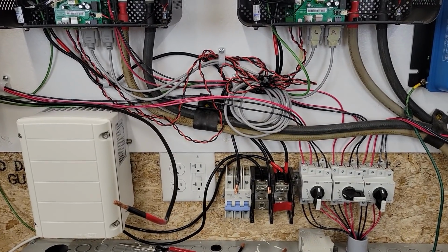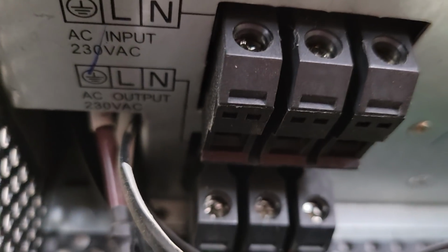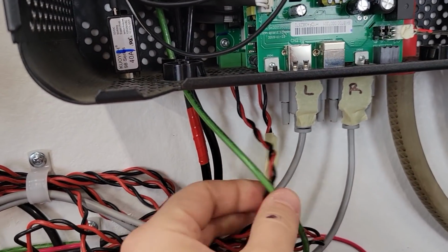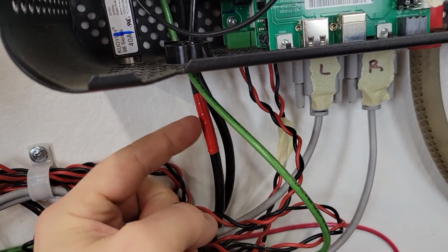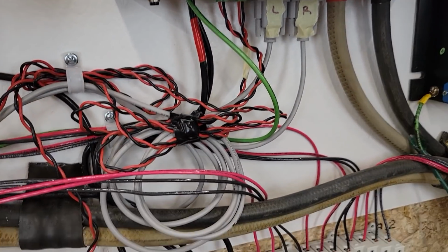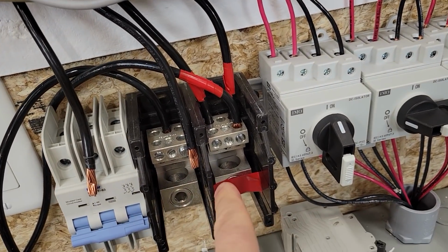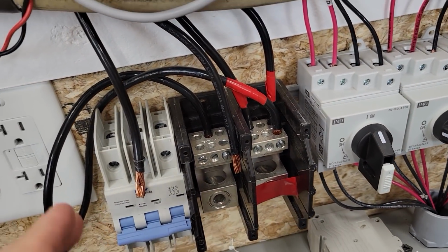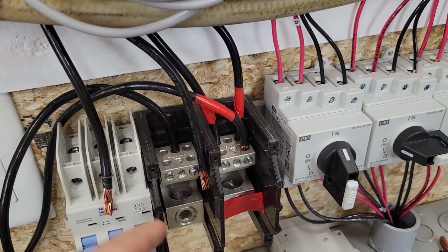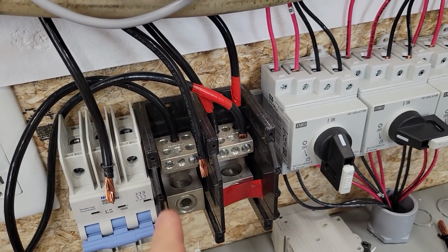Let me give you an overview of the wiring. You can see up there they have it listed as ground, line, and neutral, but I'm going to call it ground, L1, and L2. So red is L2. All the L2s come together at this terminal block, but the black ones, they used to run to this terminal block, but I'm moving them.